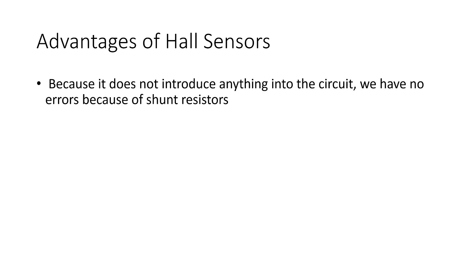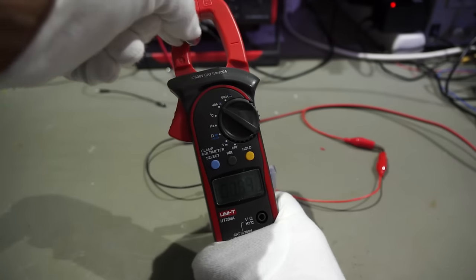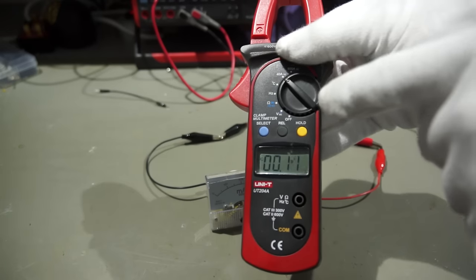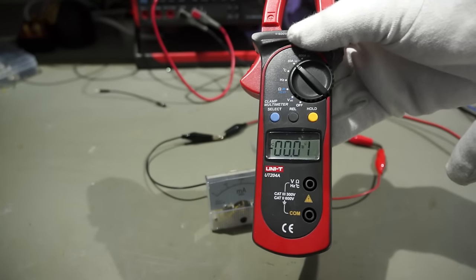These meters have three big advantages. First, because it does not introduce anything into the circuit, we have no errors because of shunt resistors. Second, because there is no connection to our circuit, we have no problems with ground loops. And third, they work for positive and negative currents. Apart from its inability to measure small currents, it has also another big disadvantage. It measures all kind of magnetic fields. If I put a magnet close to its clamp, it shows big currents. This is why these instruments have a button to zero the effects of any existing magnet fields before measuring.